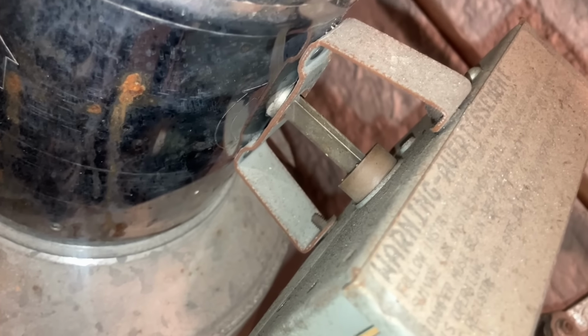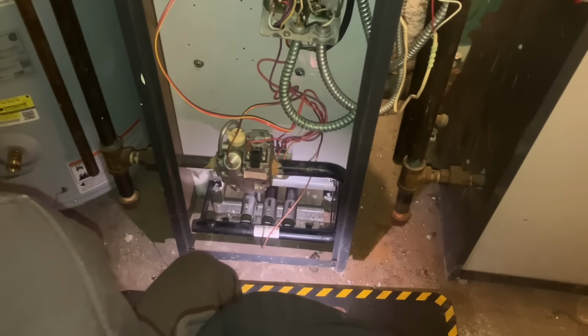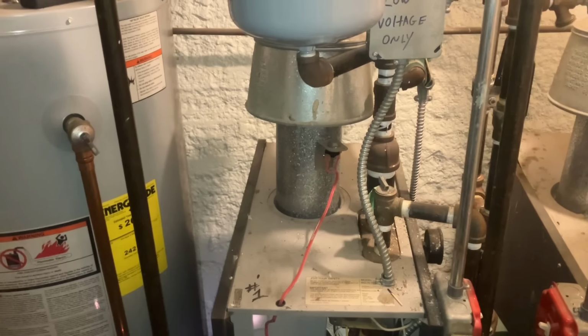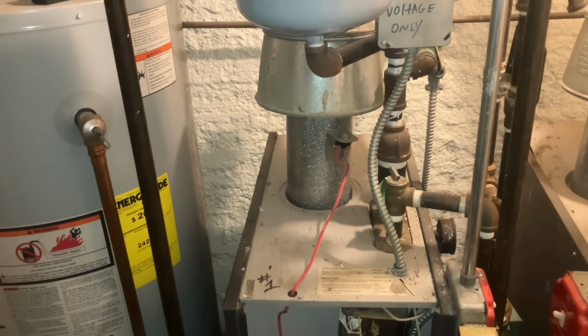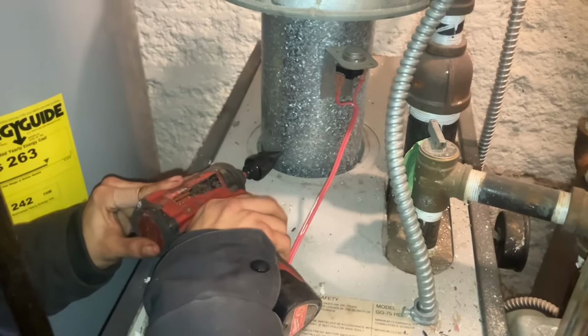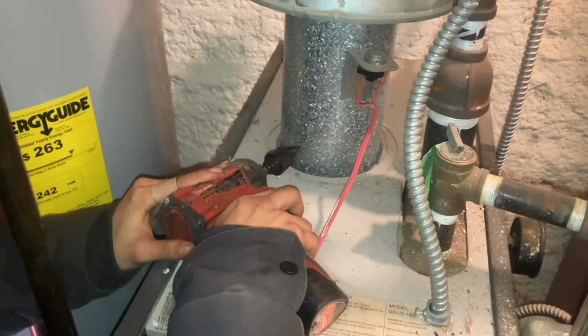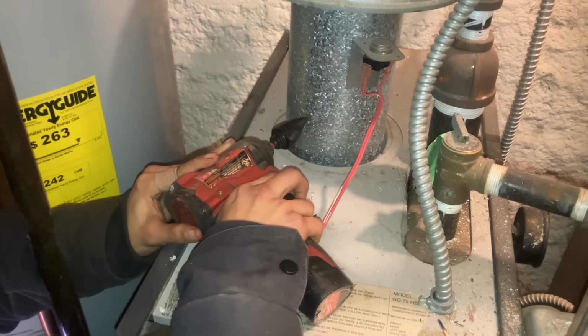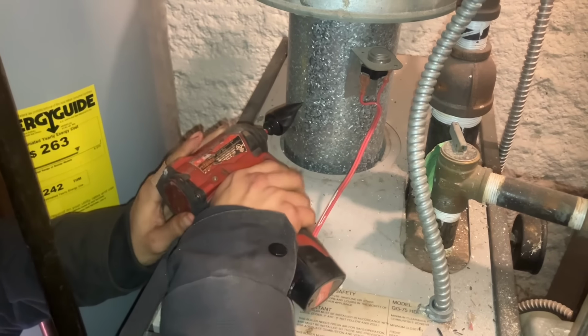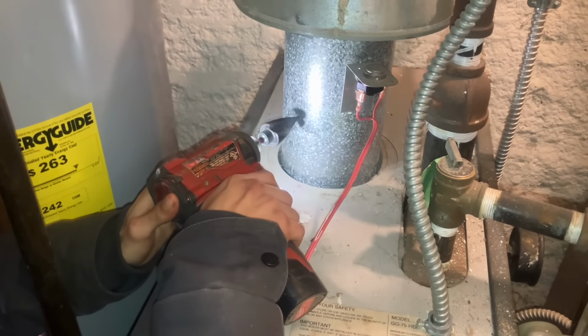Some action going on right there. There is that vent damper opening. The vent damper is open and followed by ignition. So we have ignition. Let's drill a hole in the exhaust piping to do a combustion analysis. We're going to use a step bit about 6 inches off the top of the boiler. Is that 6 inches off the top of the boiler? No. Okay, good. I'll drill a little hole there.